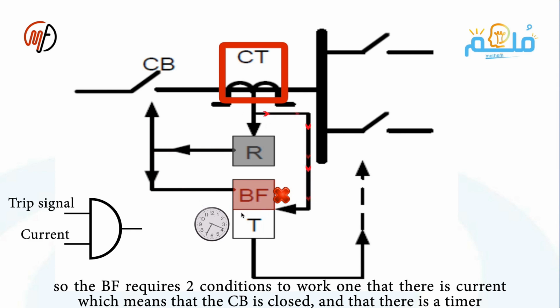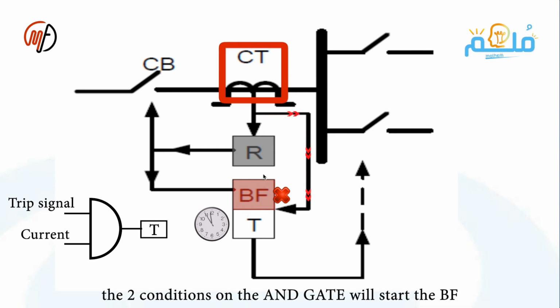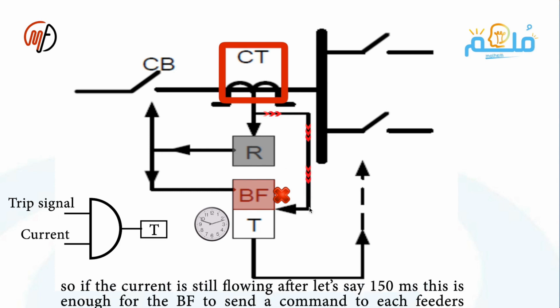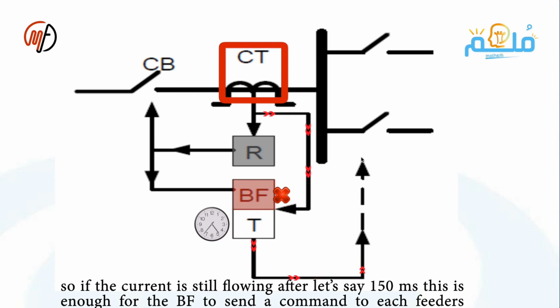If continuous current persists after a fault for 150 milliseconds, the breaker failure decides to disconnect all feeders supplying this feeder. If this feeder doesn't operate, all its feeders will be disconnected. The relay's decision time is quick, 20 milliseconds or less, plus overcurrent delay. The circuit breaker takes 50 to 100 milliseconds to open. The total time is the fault isolation time, starting from the fault occurrence until the circuit breaker opens.